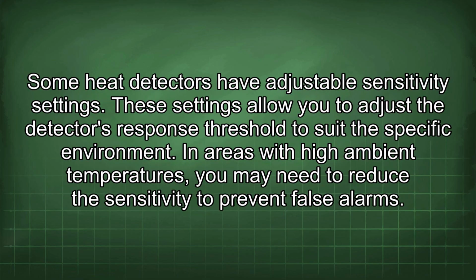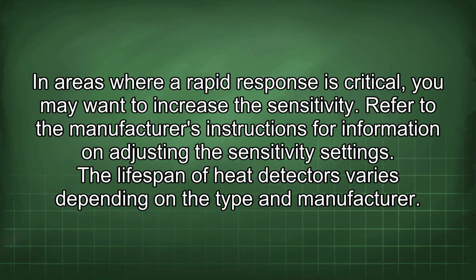Some heat detectors have adjustable sensitivity settings. These settings allow you to adjust the detector's response threshold to suit the specific environment. In areas with high ambient temperatures, you may need to reduce the sensitivity to prevent false alarms. In areas where a rapid response is critical, you may want to increase the sensitivity. Refer to the manufacturer's instructions for information on adjusting the sensitivity settings.